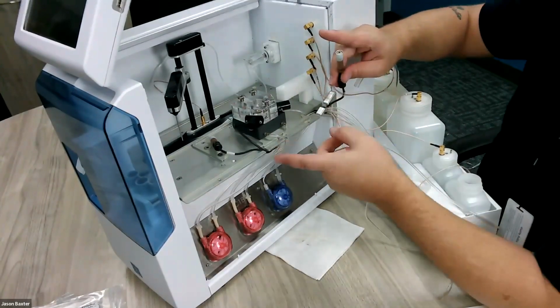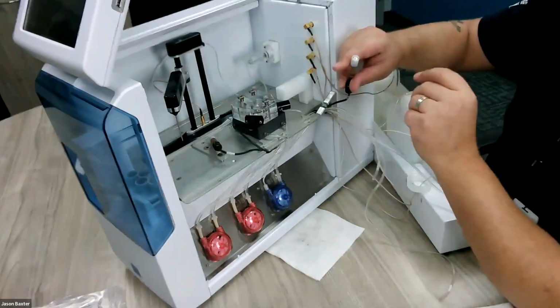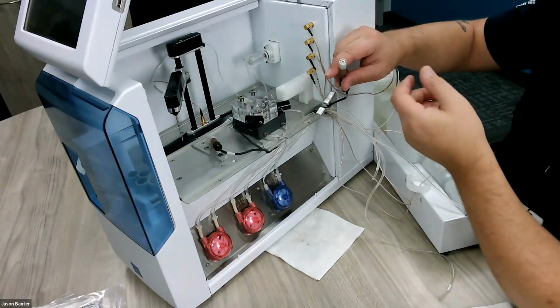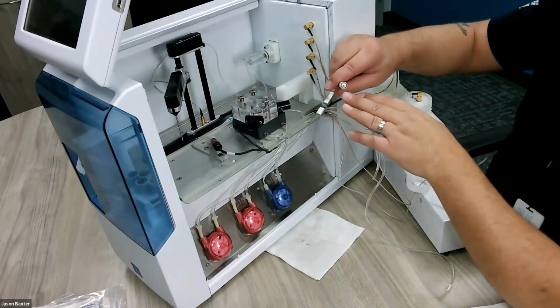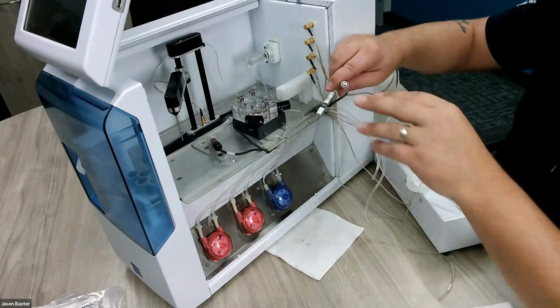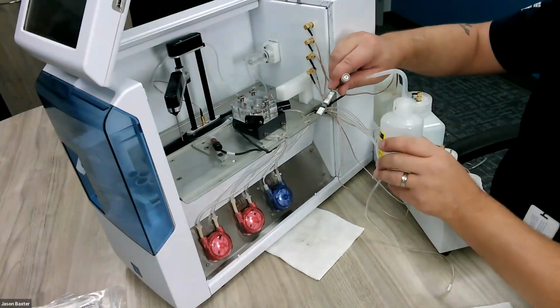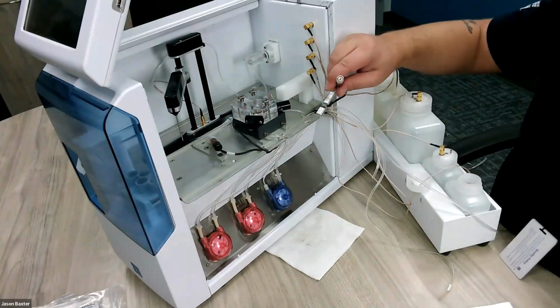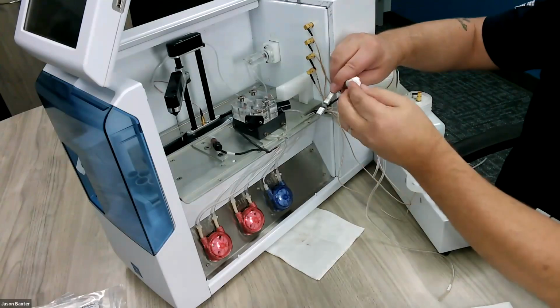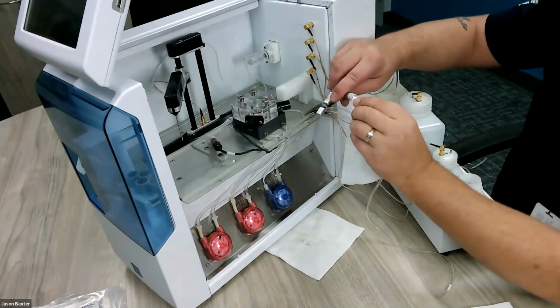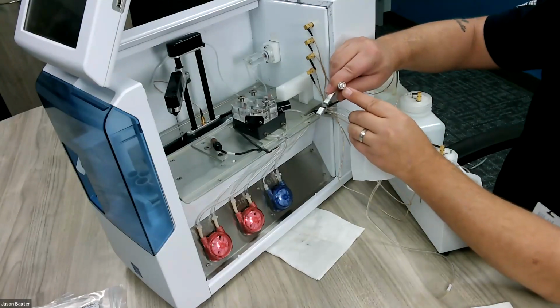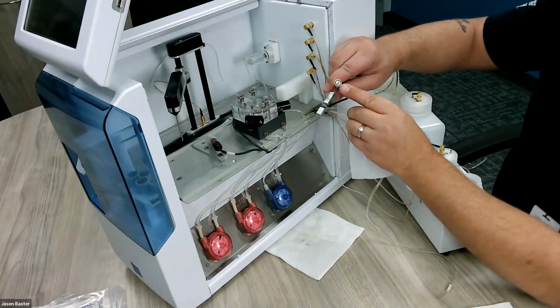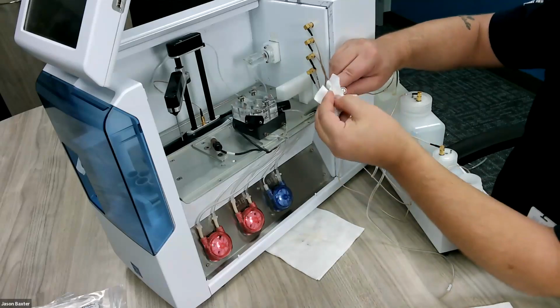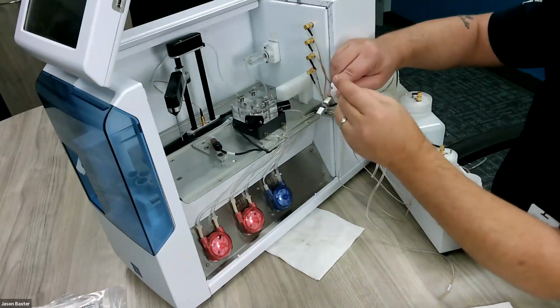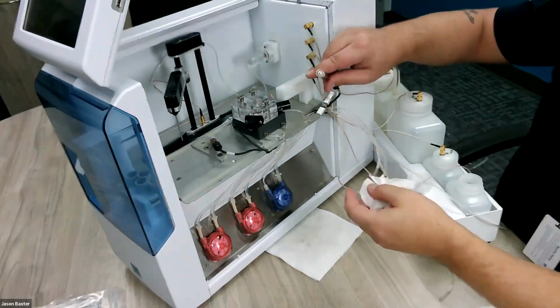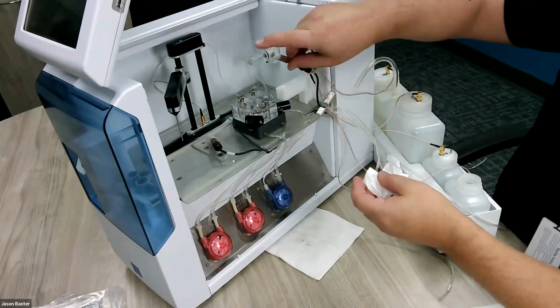So now we need to clean up the electrodes and replace the sample needle. And both of those can be done quite easily. On this electrode, you'll notice the membrane's gone, so that's kind of helpful. So you take a small amount of rubbing alcohol, dose it, and then blot it dry. What you're looking to do is remove any potential remains of an old membrane that might be stuck to the face of that electrode. So you'll blot it dry. And if you have some DI water handy, you want to rinse it with DI water.